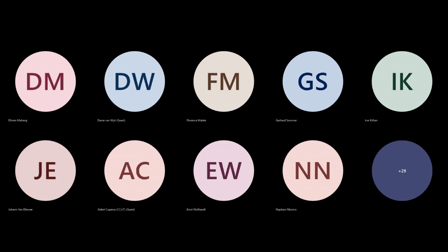Yeah, just to mention there, although we're sampling at 50 kilohertz and we give you access to high quality visuals up to 25 kilohertz, like Heinz said, anything above, say, 3 kilohertz, your conventional magnetic voltage transformer will filter out a lot of the quality information available. And specifically also, it has resonant points in the higher frequencies. So you wouldn't be certain if the higher content is attributable to the measurement transformer you're using or actually by the load or generator that you're investigating.